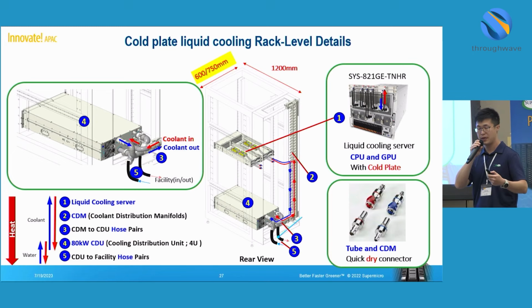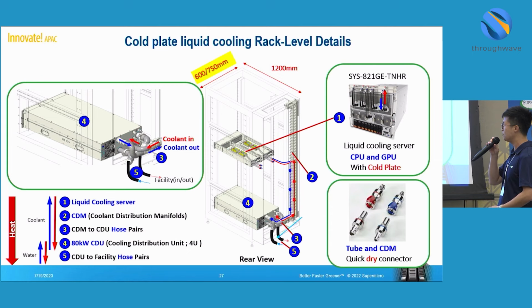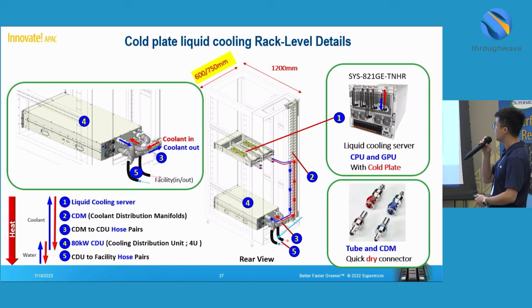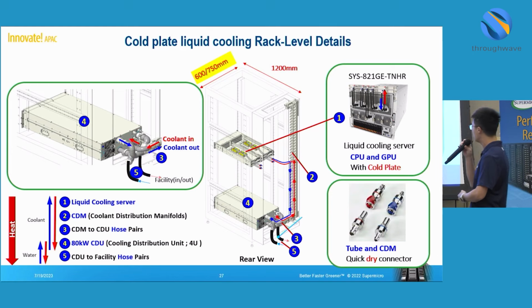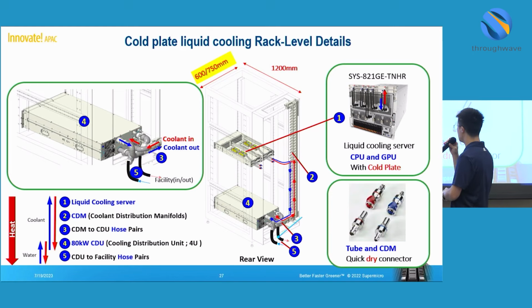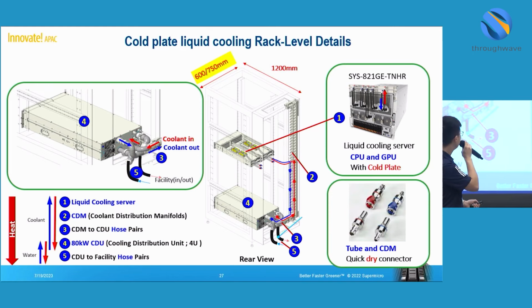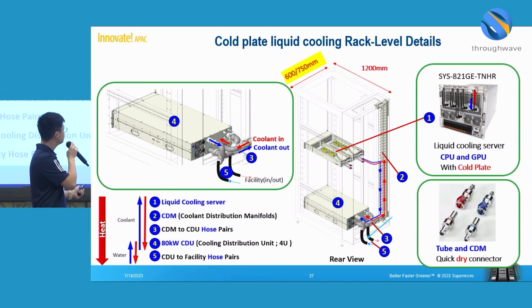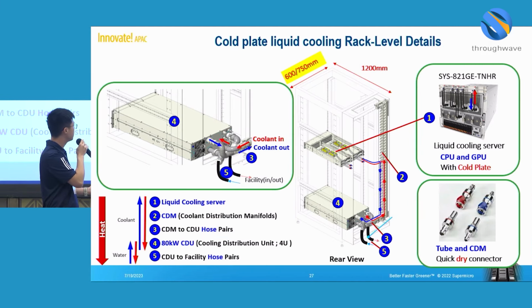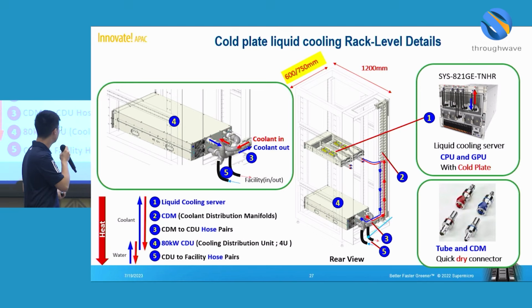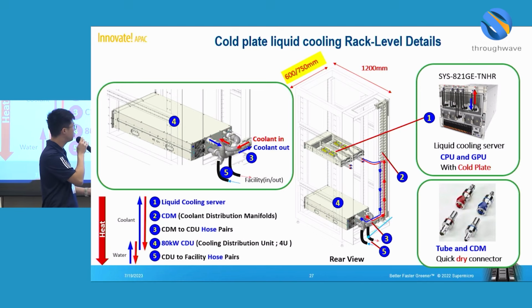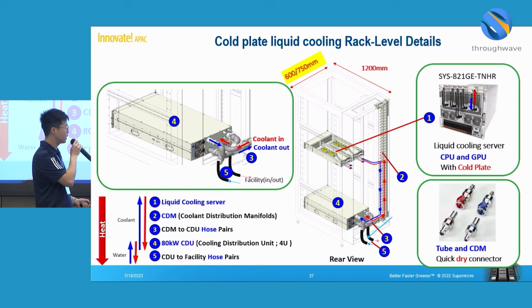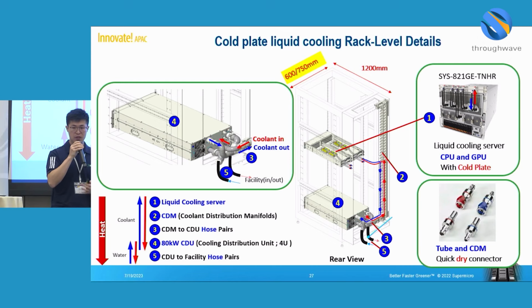So the heat is dissipated from 1 to 5 in order. The first one is the liquid cooling server, which has CPU and GPU with cold plate. The liquid cooling server connects to the CDM, which we call the coolant distribution manifold, by the tube. Both the tube and the CDM use a quick dry connector, so there is no leakage risk during connection.